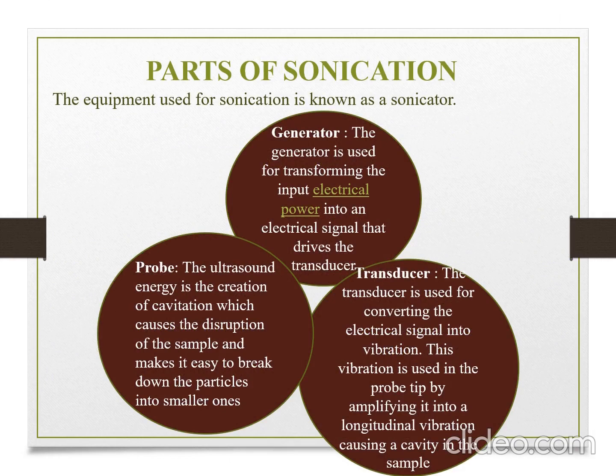The parts of sonication. The equipment used for sonication is known as a sonicator. Generator, transducers, and probes are its components. The generator is used for transforming the input electrical power into an electrical signal that drives the transducer. The transducer is used for converting the electrical signal into vibration. This vibration is used in the probe tip by amplifying it into longitudinal vibration, causing cavitation in the sample.